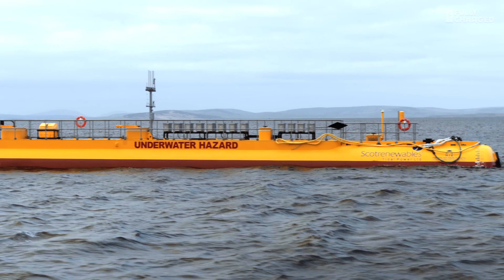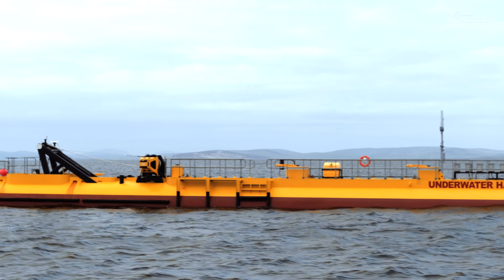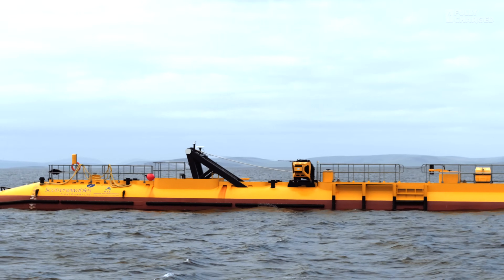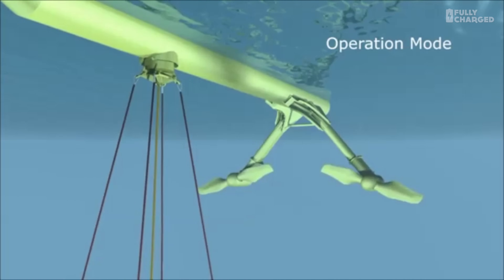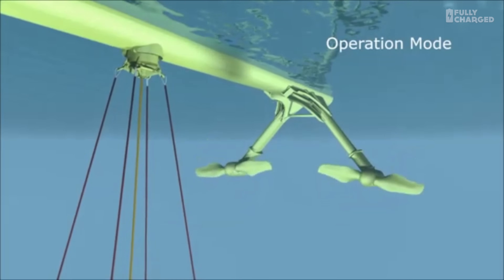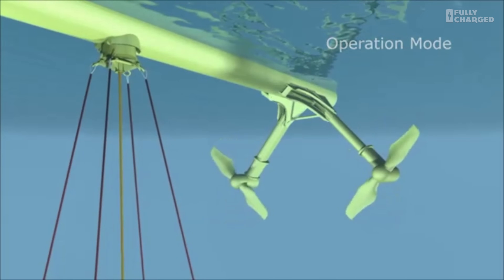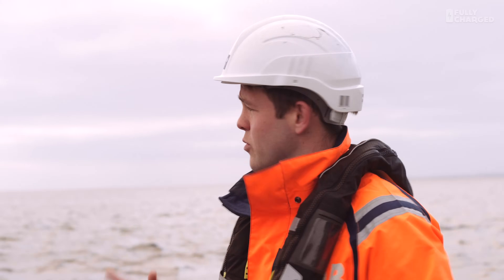Because it looks like a yellow submarine that's just come out of the water — how long is that? It's 64 meters long and weighs about 505 tons roughly. Underneath the water there's a lot you can't see — there are two huge retractable legs with rotors on the end. The turbine connects to a modular gravity anchor system on the seabed, brought up into a turret that has the electricity cable connection, and the turbine can yaw into the tide.